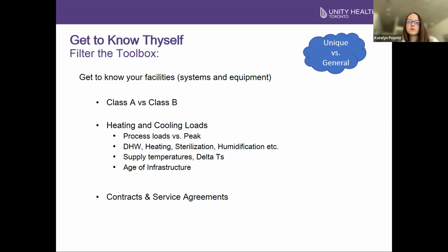It's important to understand the delta T's and supply temperatures you need to meet. In newer facilities, you might drop your supply temperature on radiant heating if you have a robust building envelope, versus an older facility where you might not have the right terminal-side technology to support a temperature change.